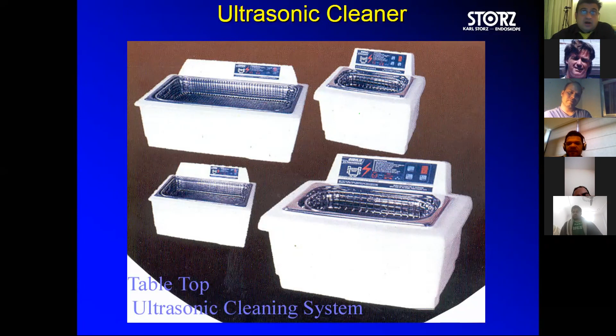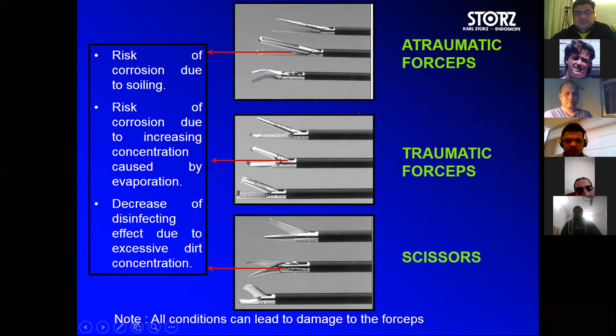Now, this is what I was trying to explain. If you see in these forceps, of course, in neuroendoscopy the forceps are still smaller, this is where you have the laser welded rivet joints. In engineering language we call them rivet joints, and they hold both jaws together to work. And this area is not properly cleaned. Due to corrosion and induced chloride pitting coming from another instrument, the rivet joint breaks, and then the repairs are expensive at the end of the day. So we can avoid this by doing this periodic cleaning.